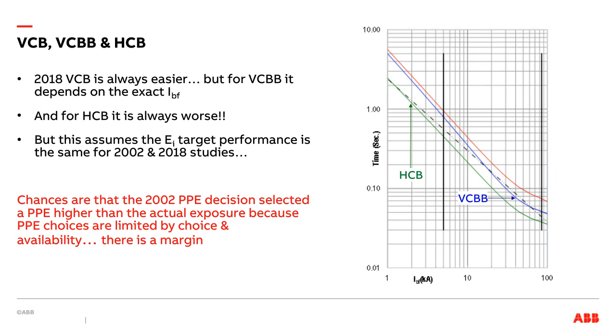So what is calculated for a particular piece of equipment, let us say a switch or a switchboard, may be 4, 5, 6, 7 calories. But the recommendation in the arc flash label, or the arc flash study, will suggest 8 calorie PPE. The practice at that facility is 8 calorie PPE, or maybe 12. So there's a margin between the PPE that would normally be used for that task and the old calculation for arc flash. The question would be, is that margin enough to cover the difference between the old calculation and what a new calculation would give you? And I'm suggesting that this is a method to estimate that conservatively.